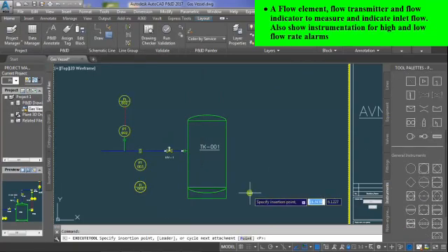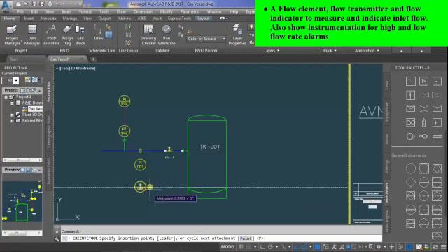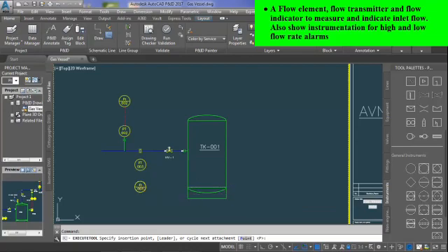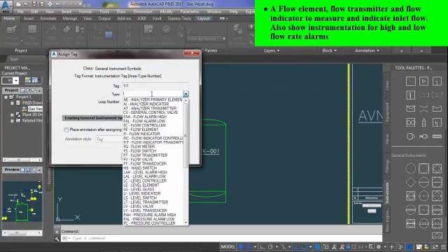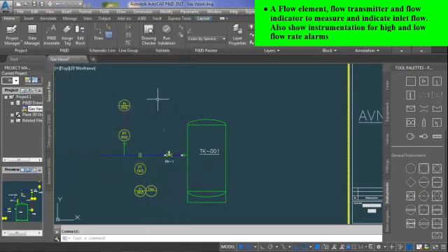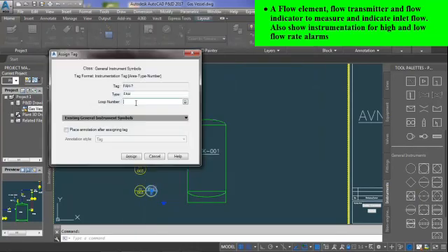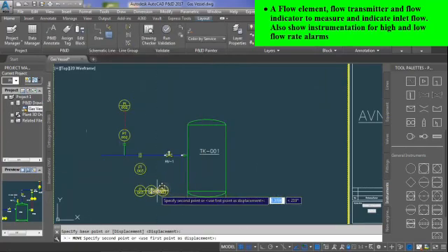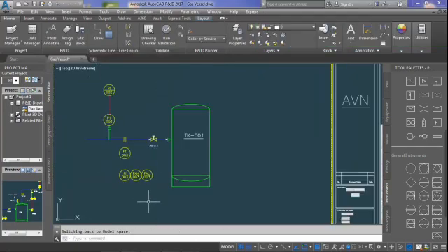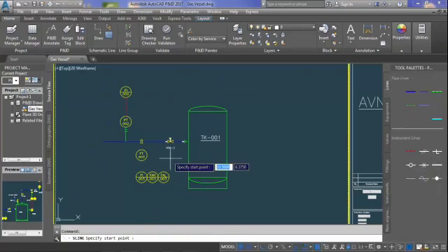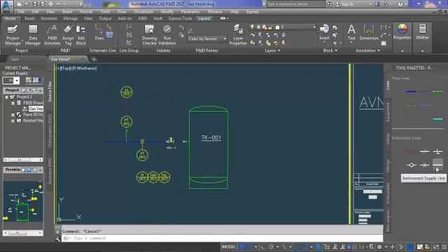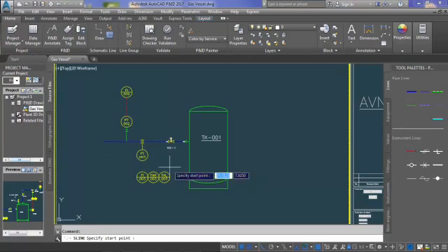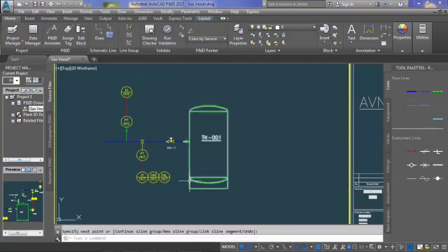Then also insert instruments for alarms to show that in this flow monitoring we have to monitor high and low flow rate alarms. Steps to insert alarms are the same as flow indicator. Just for flow alarm high, tag FAH-3, and for flow alarm low, tag FAL-3. Then use electrical line to join the flow transmitter with the flow indicator.